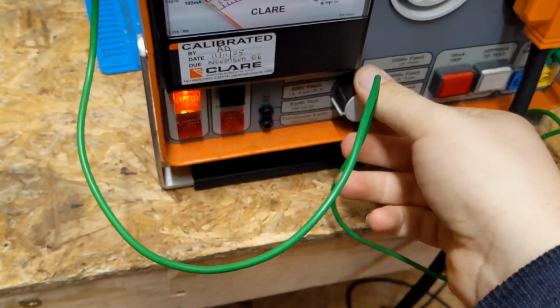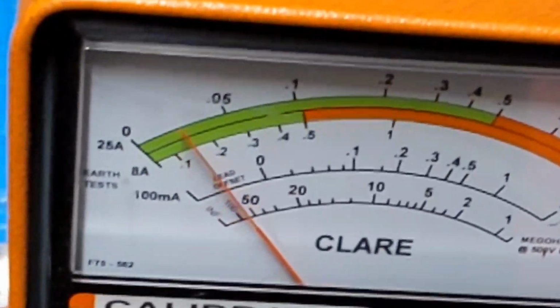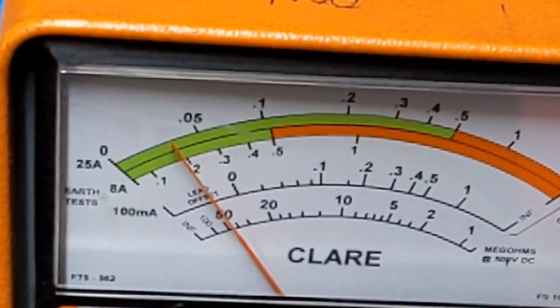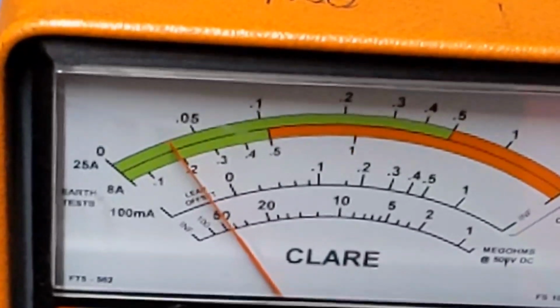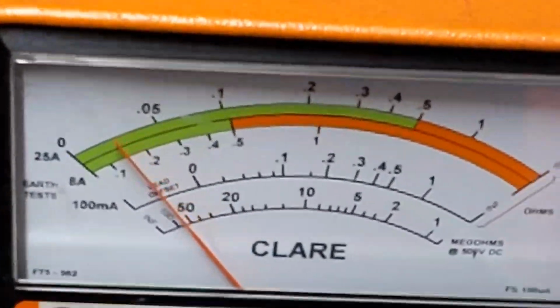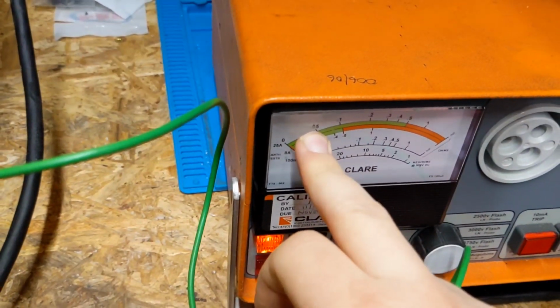So what we're doing is plugging it in there, grabbing our earth wire, connecting that onto the top like so, turning the little knob to high current earth test, and testing. You can see we're getting quite a good reading - hold it on for a couple of seconds. We're getting 0.05 ohms, which is good. For something like this, we'd expect something less than 0.1 ohm. So a nice short cable, the earth is good.